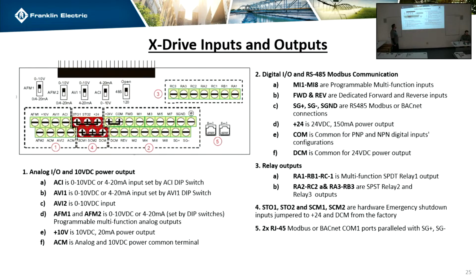All right, here's the input and output breakdown from the drive. All of the inputs have multiple functions, and so there's a dip switch that switches between the two. This is how it's going to be set up default. ACI is 0 to 10 or 4 to 20 with a dip switch. AVI 1, 0 to 10, 4 to 20 with a dip switch. So the same functionality, two options. We will wire to ACI by default.